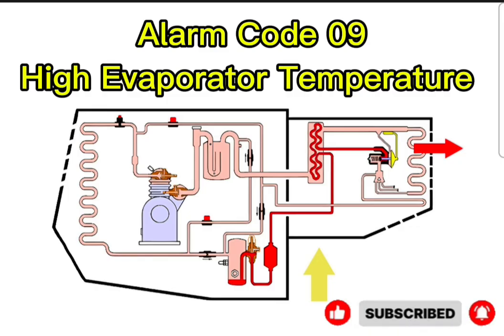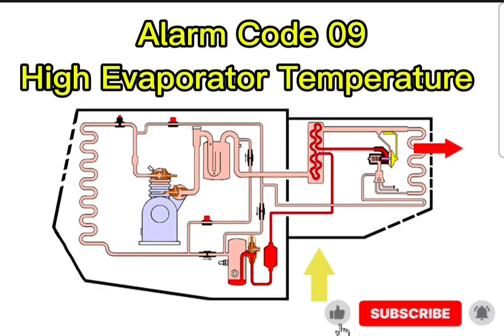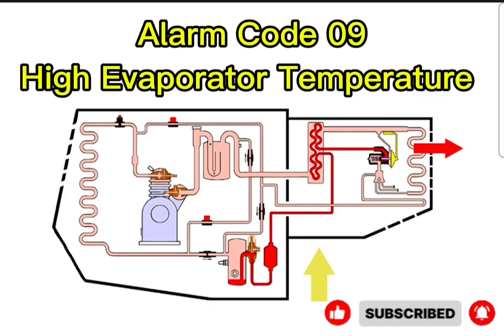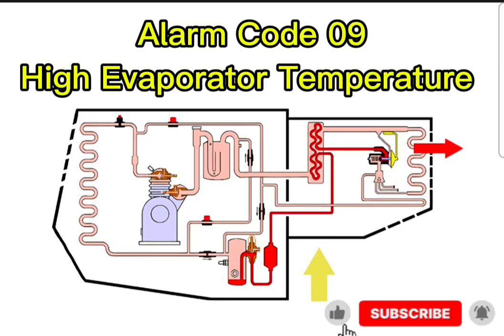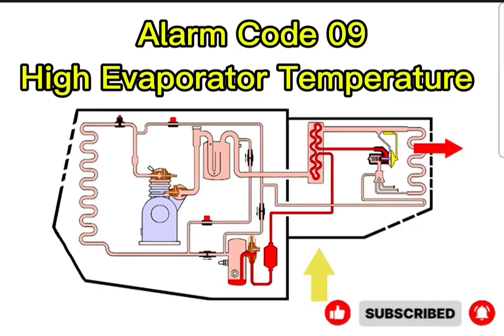That is a brilliant and, frankly, terrifying parallel. Automated systems do not possess common sense. They just don't. A human technician can put their hand on the metal housing and instantly know, this isn't 155 degrees, it's freezing. The sensor is lying. Yeah. But the microprocessor cannot cross-reference reality. It can't say, wait, the hot gas solenoid isn't even open and the compressor's in cooling mode, so it's thermodynamically impossible for it to be 155 degrees right now. It just blindly obeys the false data.